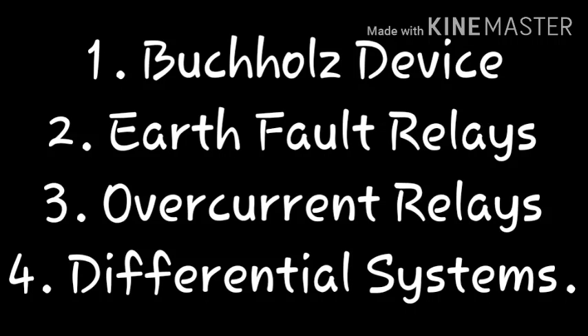The principal relays and systems used for transformer protection are Buchholz relay, earth fault relays, overcurrent relays, and differential systems. Buchholz relay provides protection against all kinds of incipient fault. What is an incipient fault? A slow developing fault such as insulation failure of windings, core heating, fall of oil level due to leaky joints, etc. Earth fault relays provide protection against earth fault only. Overcurrent relay provides protection against phase to phase faults and overloading. Differential system or circulating current system provides protection against both earth and phase faults.